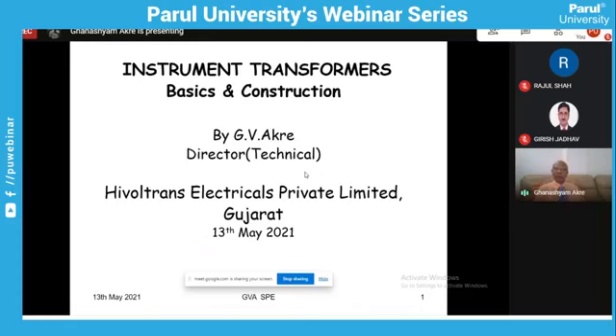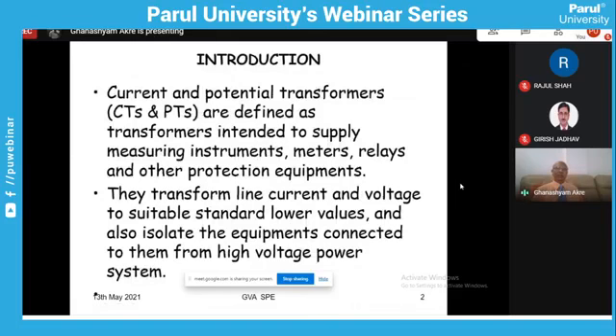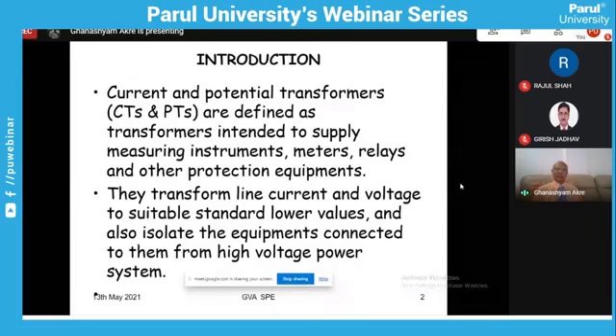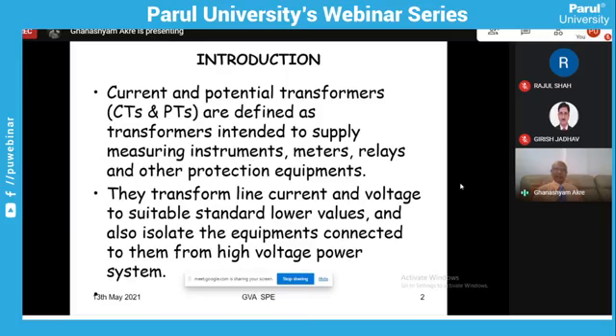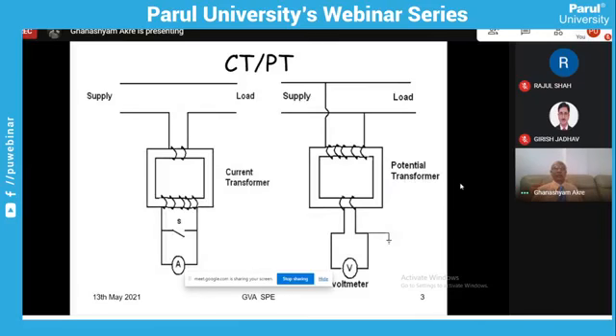So friends, now I will straightway come to the principle of this. Now, what is the current transformer? Current and potential transformers are defined as transformers intended to supply measuring instruments, meters, relays, and other protection equipment. They transform line current and voltage to suitable standard lower values and also isolate the equipment connected to them from the high voltage system. From this schematic diagram, you can see there is a current transformer at left side and a potential transformer at right.